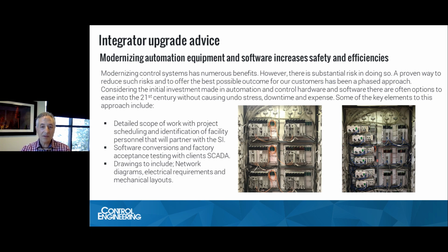After acceptance testing, we installed the new hot standby CPUs, which you see on the right-hand side, which continue to service the existing remote I/O network, which, as I said, is over 100 racks.